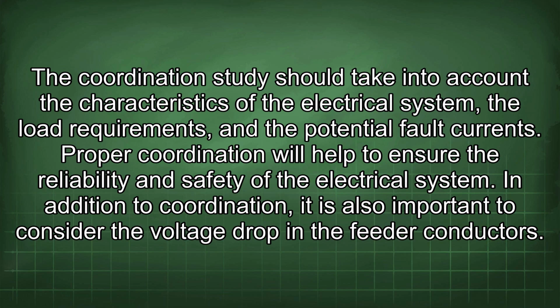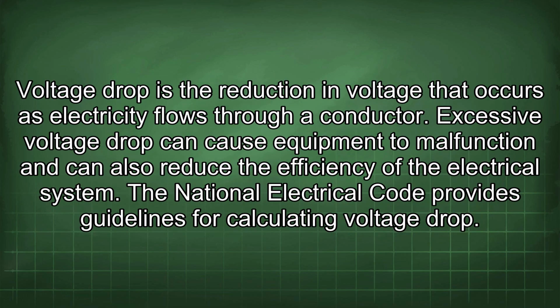In addition to coordination, it is also important to consider the voltage drop in the feeder conductors. Voltage drop is the reduction in voltage that occurs as electricity flows through a conductor. Excessive voltage drop can cause equipment to malfunction and can also reduce the efficiency of the electrical system. The National Electrical Code provides guidelines for calculating voltage drop.